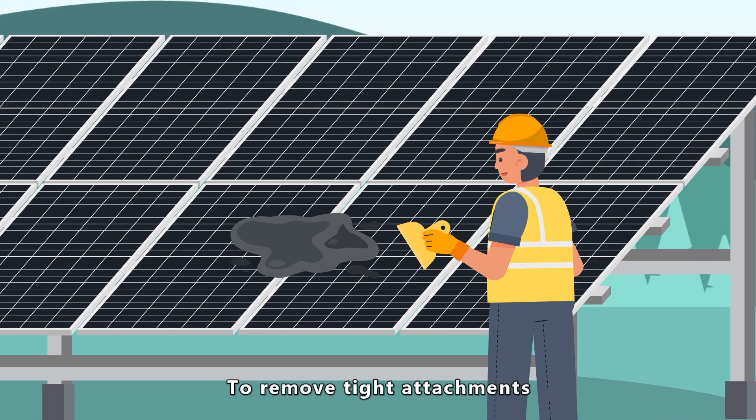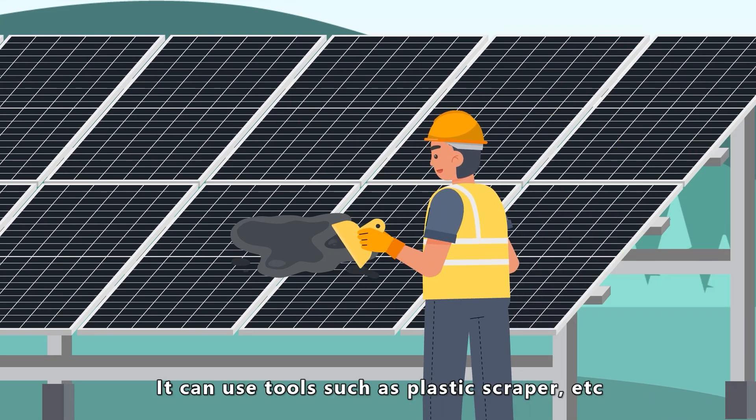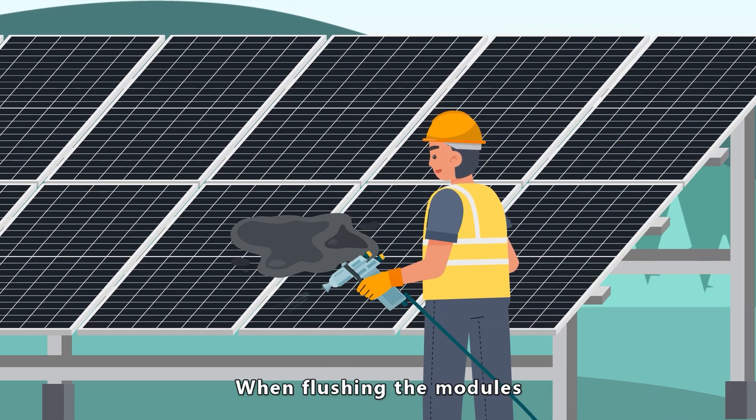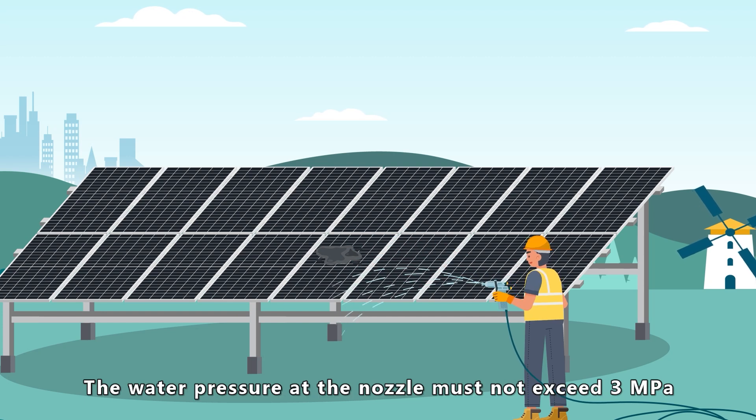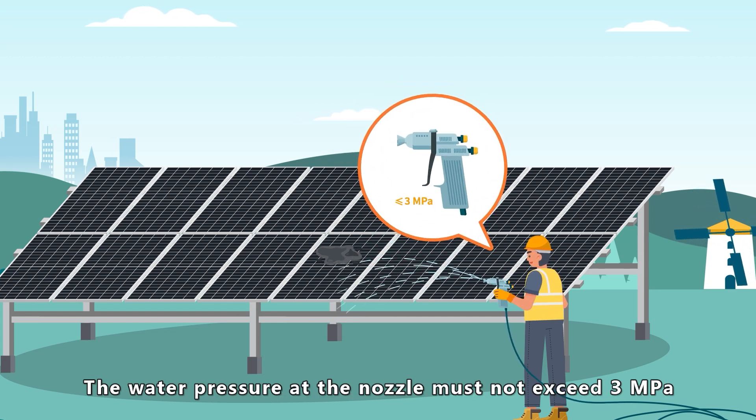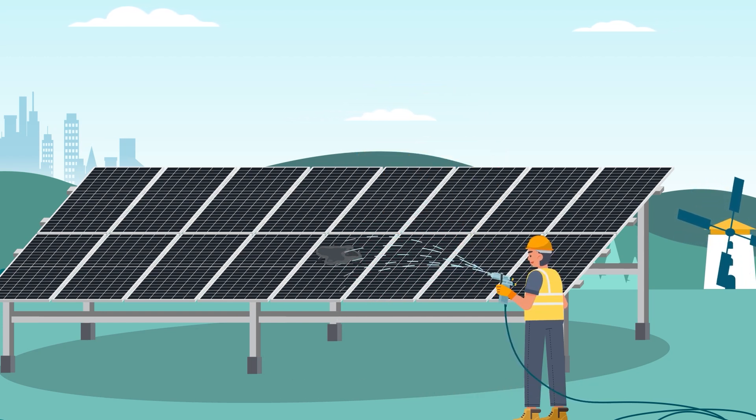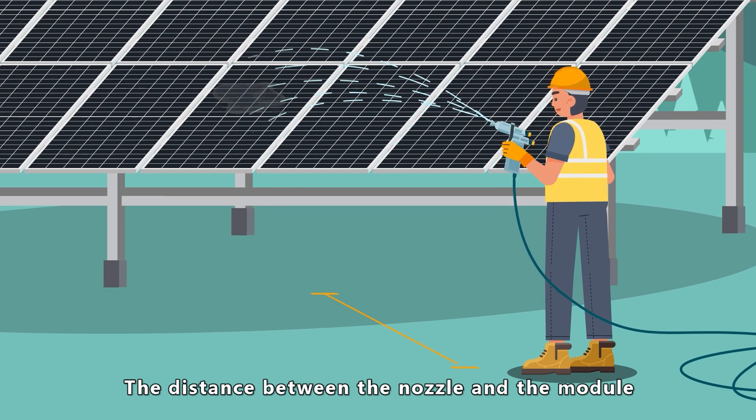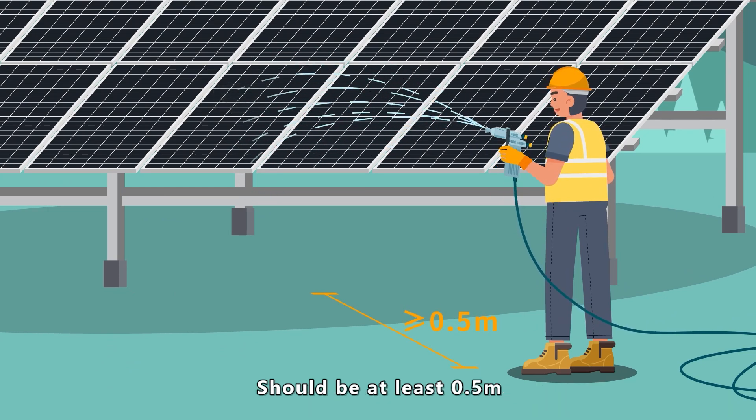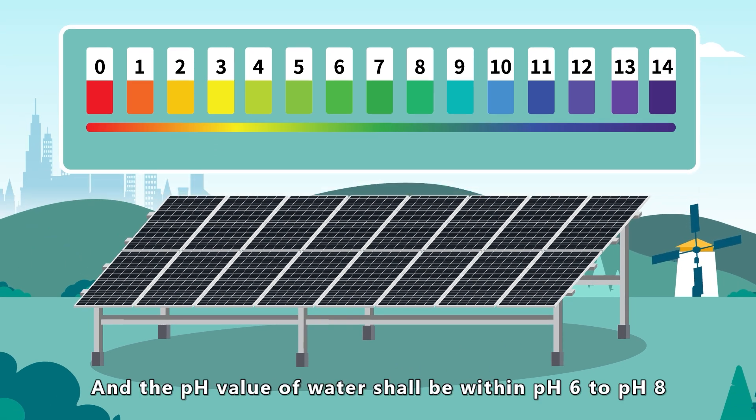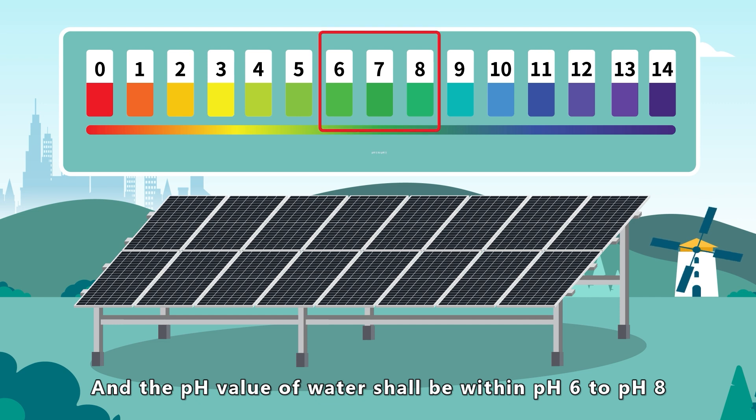To remove tight attachments, use tools such as plastic scrapers. When flushing the modules, the water pressure at the nozzle must not exceed 3 MPa. The distance between the nozzle and the module should be at least 0.5 meters and the pH value of the water shall be within pH 6 to pH 8.